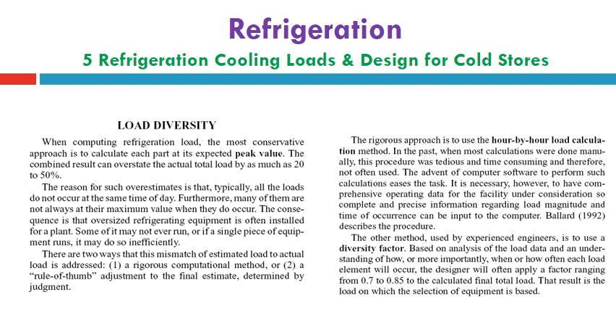Ballard describes this procedure. The other method, used by experienced engineers based on their experience, is to use a diversity factor based on the analysis of the load data and an understanding of when or how often each load element will occur. The designer will often apply a factor ranging from 0.7 to 0.85, not higher or lower than this range, to calculate the final total load. As a result, this is the load on which the selection of the equipment is based during the final design stage.